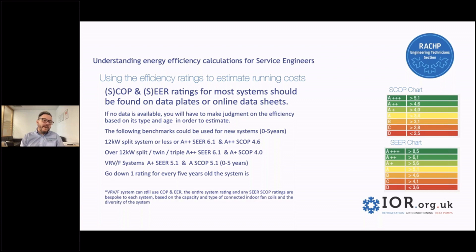VRV and VRF systems are a bit more complicated. If it were a modern system, I'd probably be looking at a EER rating of 5.1 and a SCOP of 5.1 for 0 to 5 years old. Bear in mind that VRV and VRF systems tend to use the COP and EER rating on their data plates, because the entire system rating is bespoke for everyone — it's related to how many fan coils are attached, the diversity, the types of fan coils, and everything. Every VRV is completely different, but you've got to start somewhere. If you're going to make a calculation, 5.1 is not far out.